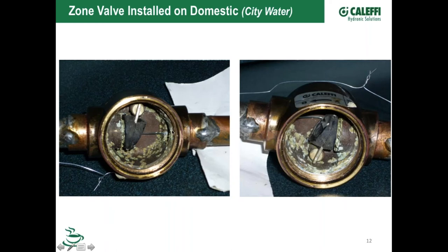It also affects our components. A lot of the components we make at Caleffi can be used for domestic water - they're low lead compliant valves. Here's an example of a zone valve that got shipped back to us after being used on a domestic water system. You can see the lime scale from whatever was in the water sticking to the brass. The good news is since we use a peroxide-cured EPDM paddle, we didn't get buildup on the paddle itself, even though the flapper was starting to bind up a little from the minerals building up around it.